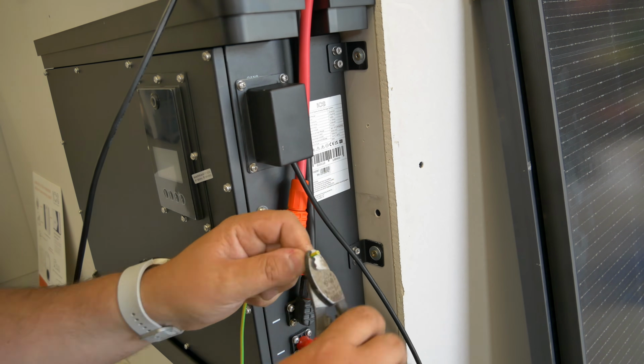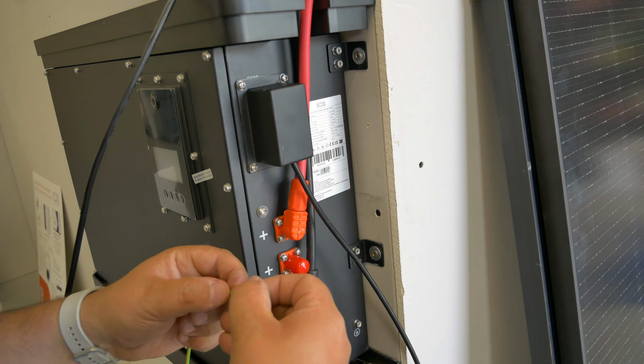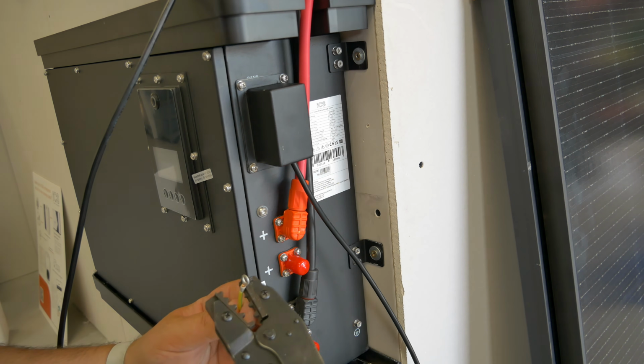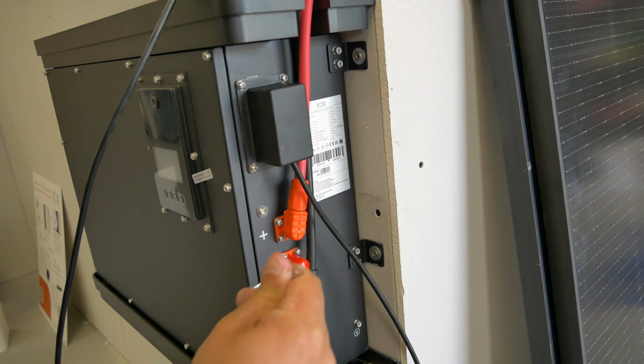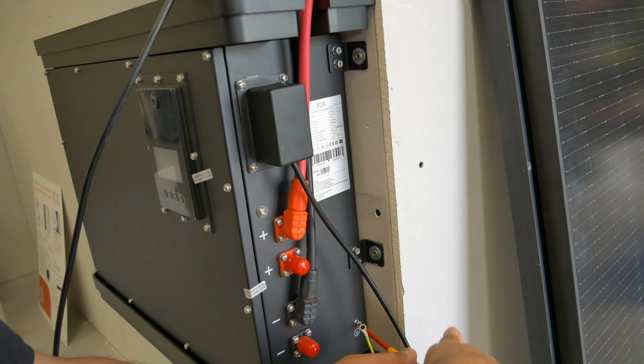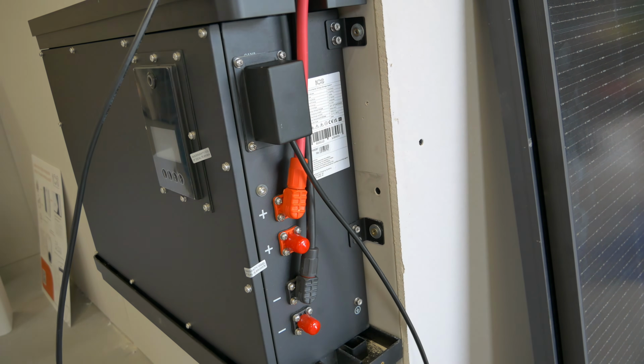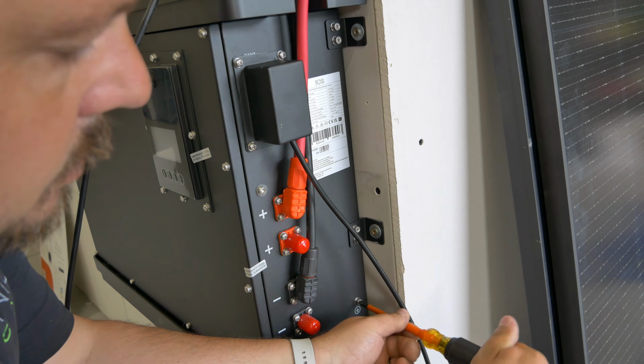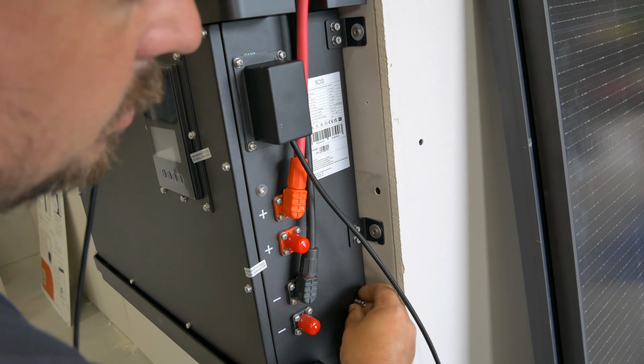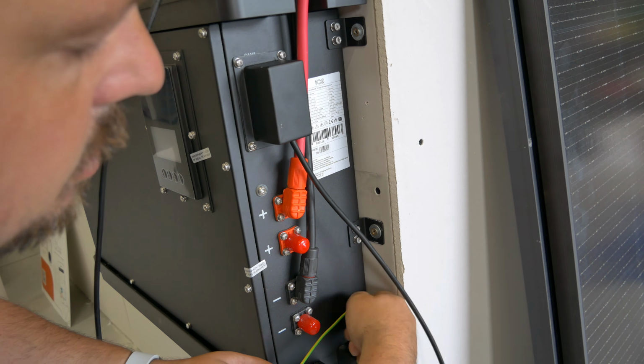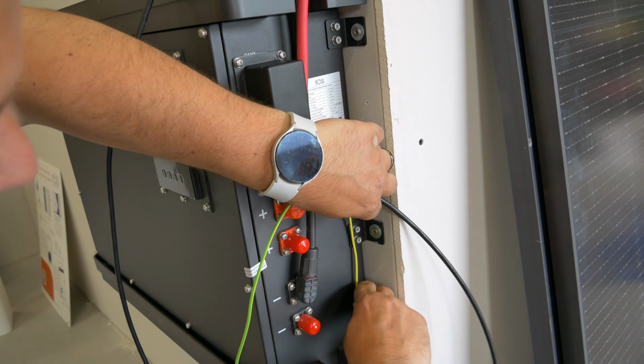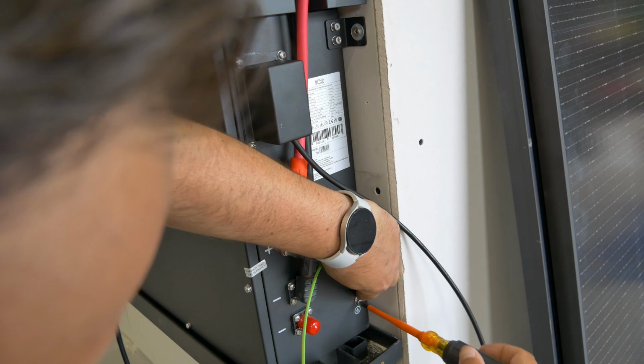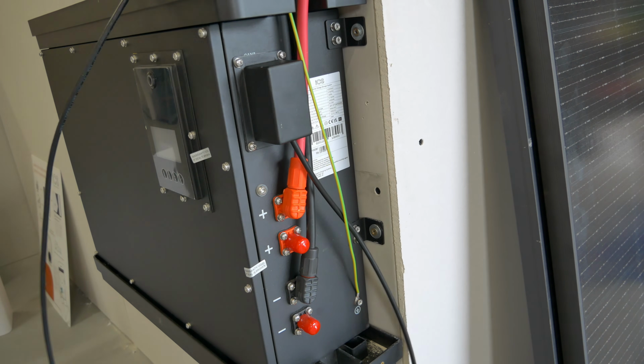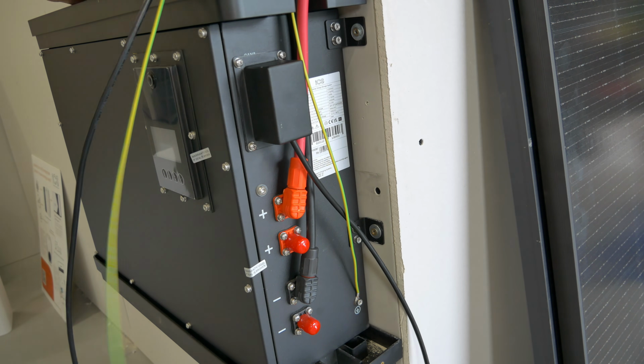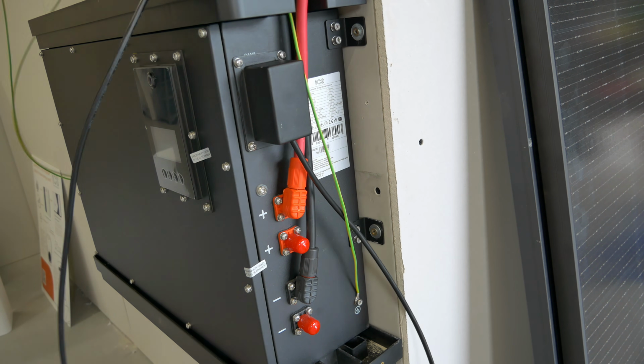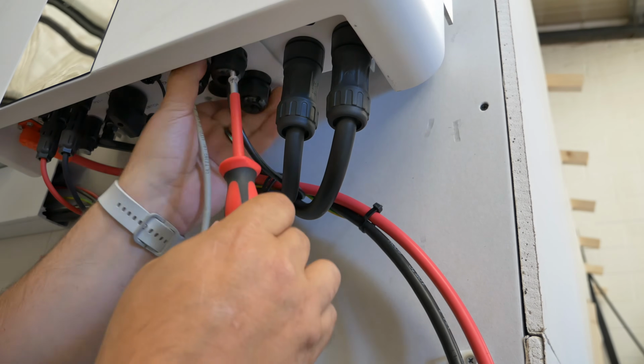We need to make off earth connections for both the inverter and the battery. It's important this is done, so we're crimping a lug to the end and connecting that into the earth terminal. Again, that's duplicated on the inverter itself, and they run off to the earth terminal supply in this equipment. It's important this is done so that, in the worst circumstances, there's a reliable earth connection to the body casing of both bits of equipment. So we're just getting that done and over with.